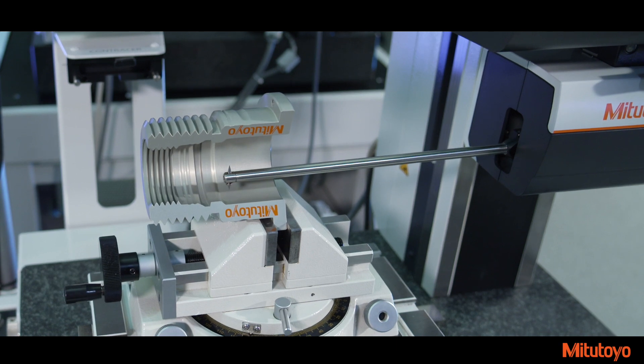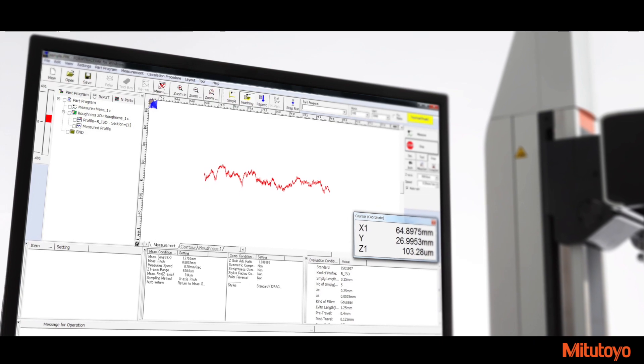The C4000 detector offers a new stylus protection function, which controls the downward movement of a stylus. Utilizing the current Mitutoyo Form Trace Pack software, the downward motion is slowed so the stylus can be detected when dropping off an edge during measurement. This reduces the risk of damaging the stylus tip.